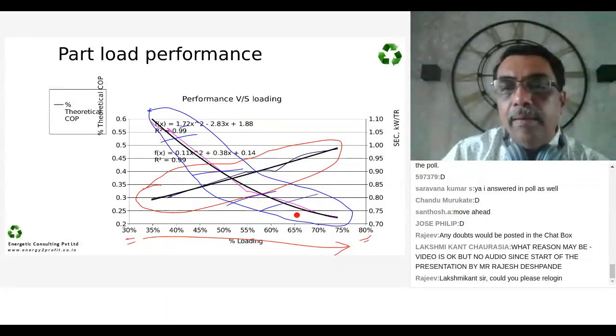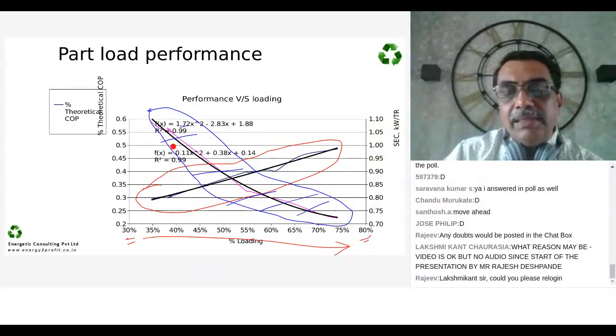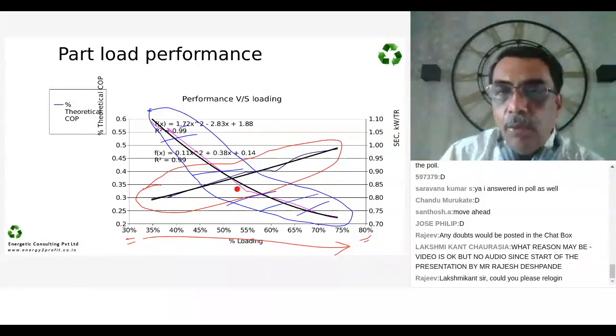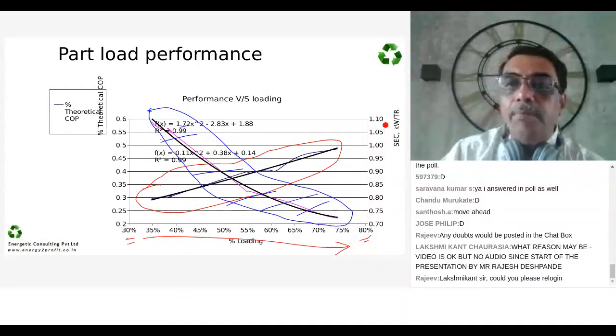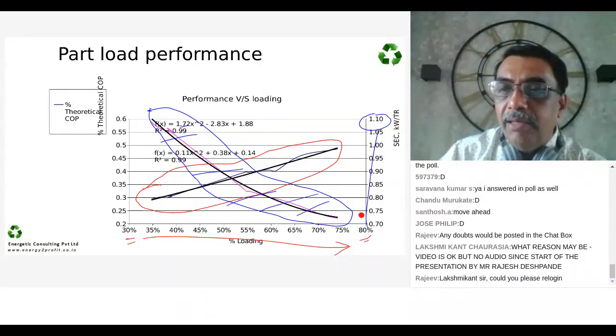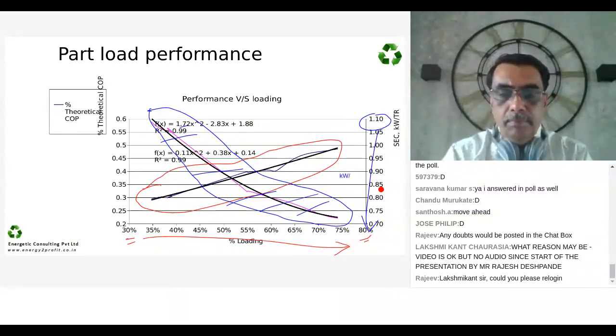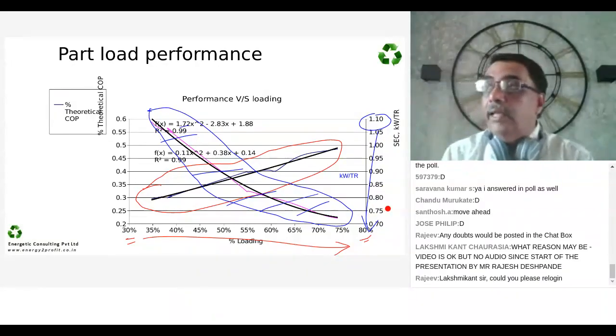This is a kilowatt per TR line. As the loading started to increase, my specific energy consumption started to reduce from almost 1.1 kilowatt per TR to 0.7 kilowatt per TR. This is very important that as loading, now in real life, how do you improve loading on your machine? We are going to see some examples of that.